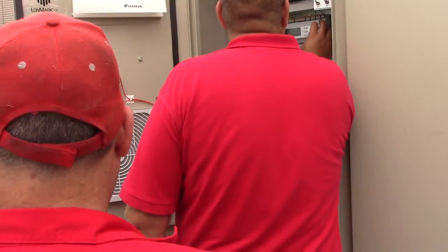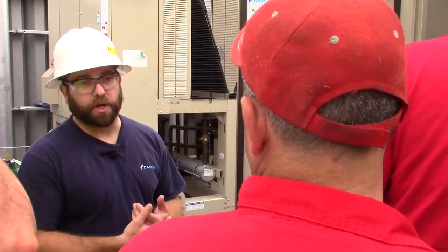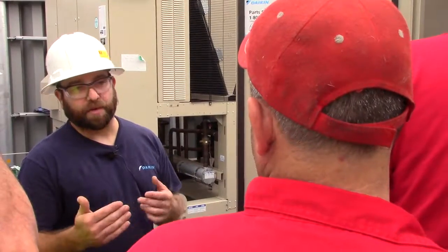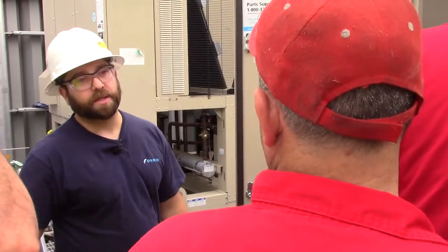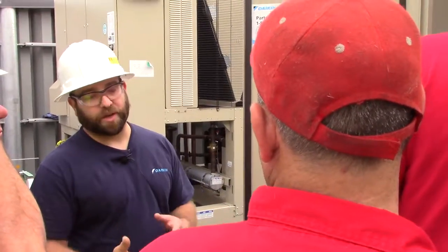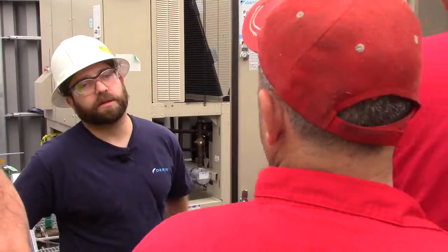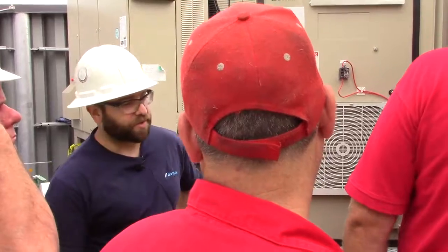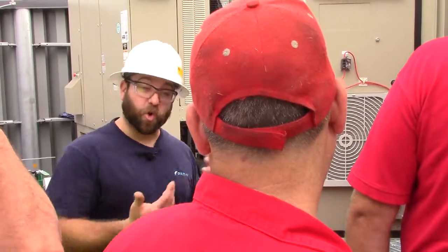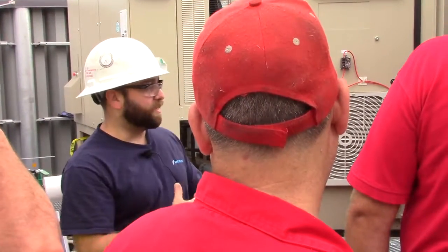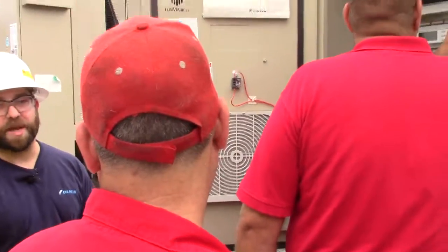Yep. For the most part, and I have to check the mills to see exactly where the spec line hits, but usually it's around 10%, believe it or not. It may be slightly above that, 12, 15, but usually it's no more than 20 of actual full load capacity. They have that ability to unload. Without looking at the submittal, I'm going to say somewhere probably between 15 and 20, but in theory it could be as low as 10, depending on the application. As long as the minimum flow conditions, bypass valves and all that stuff are controlling properly and installed and set up properly, this thing can turn down really low, sit there at minimum flow, run at minimum speed, doing within a degree of set point.